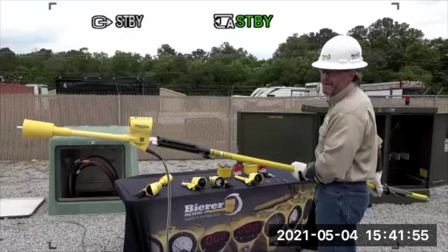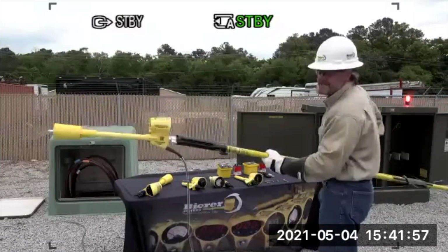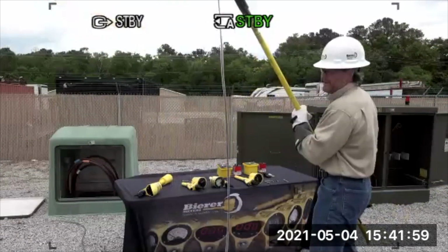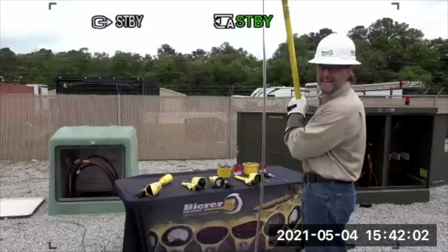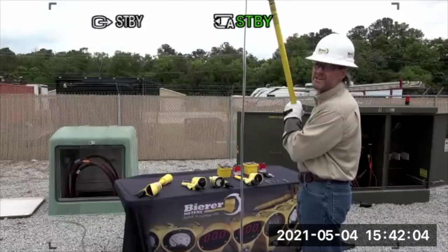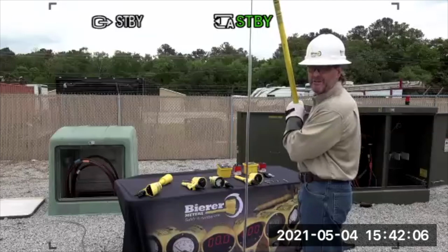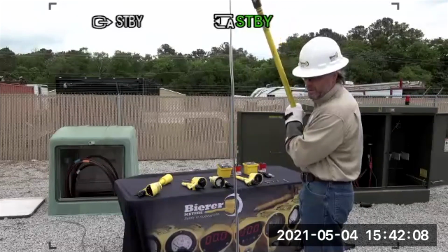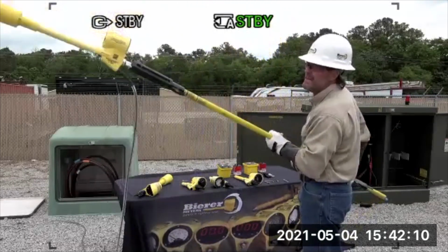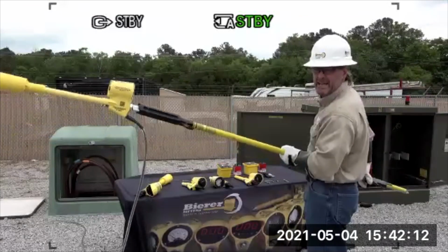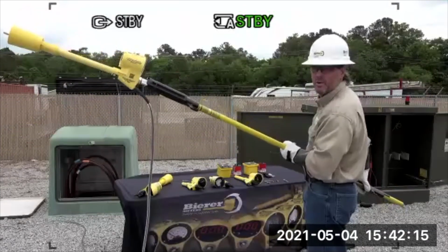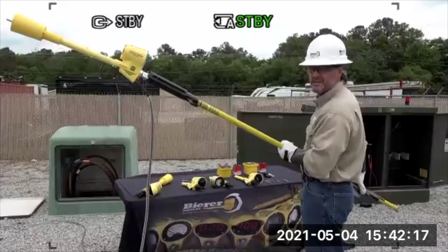If that cord became energized, maybe you're 36 inches back from the tool, but the cord's right next to my body, and if that cord becomes energized, I could get an arc flash. So the work methods need to state that the same distance from the meter head is treated the same for the cord. Let's say 36 inches.